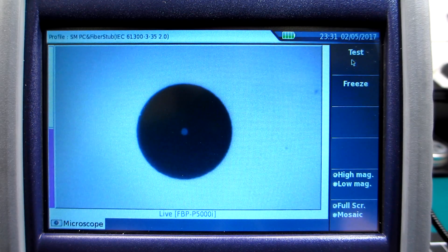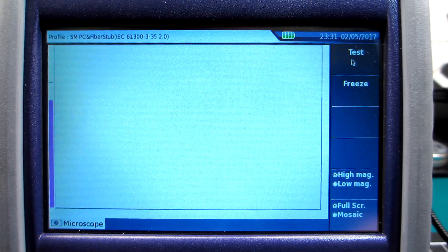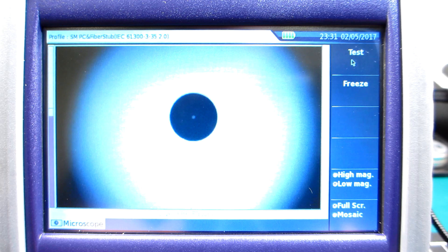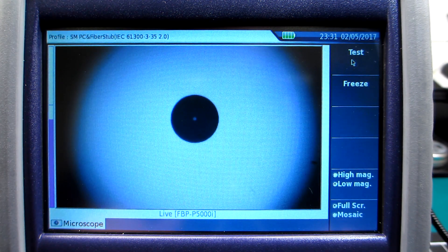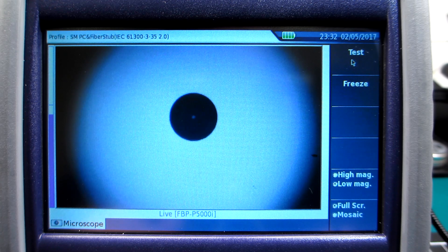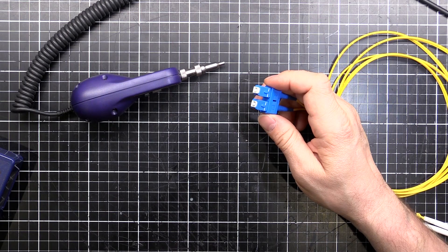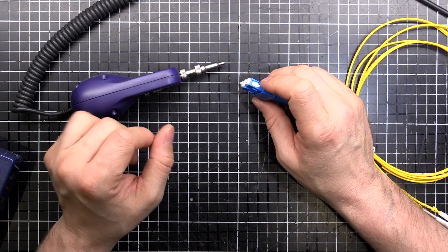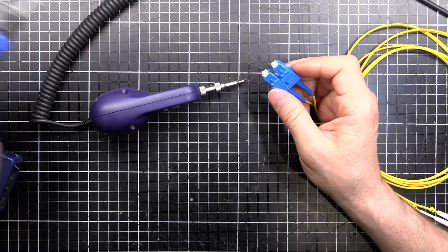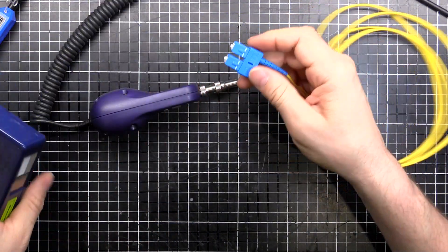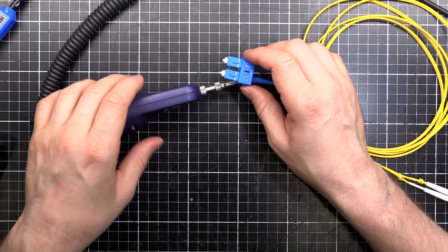I'll go to live view. And there we go. Oh there's a little bit on the side there. Hang on. And there we go. Perfectly clean, ready to go back into service. Very easy to get dirty. Don't touch the end. And putting on your shirt might make it clean-ish but it's not going to be optimum. You need a proper cleaner like a cleaning pen or like one of these wipes sort of style ones. And then you're going to be perfectly clean. And you know you're going to get a good signal.